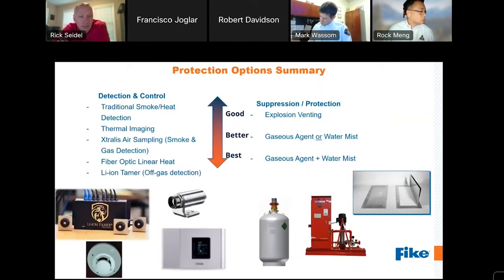If we were to try to put these on a scale from good to better to best, you'll see that your traditional spot or smoke detection up at the top is good, but your linear heat detection and your off-gas detection is the best. Same thing from a suppression or protection standpoint. Having a level of explosion venting, which we haven't discussed here, but is a requirement for these units, offers you at least a level of protection. But obviously, when you get into the gaseous agent or the water mist systems, partnered with one of those advanced detection mechanisms is clearly the best.